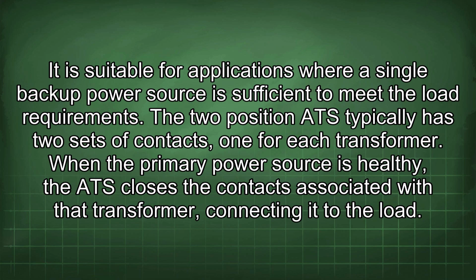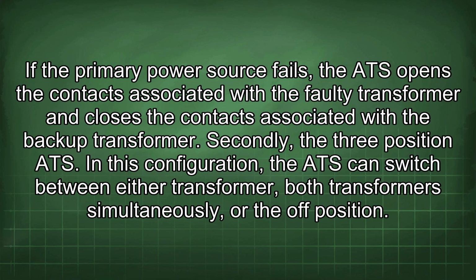The two-position ATS typically has two sets of contacts, one for each transformer. When the primary power source is healthy, the ATS closes the contacts associated with the transformer, connecting it to the load. If the primary power source fails, the ATS opens the contacts associated with the faulty transformer and closes the contacts associated with the backup transformer.